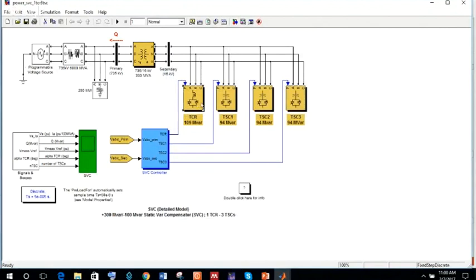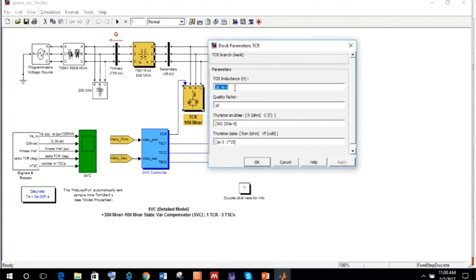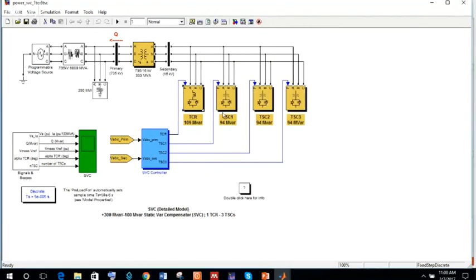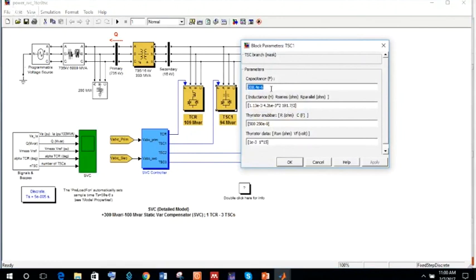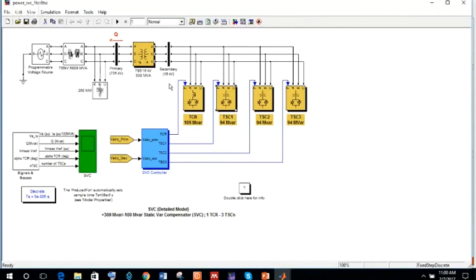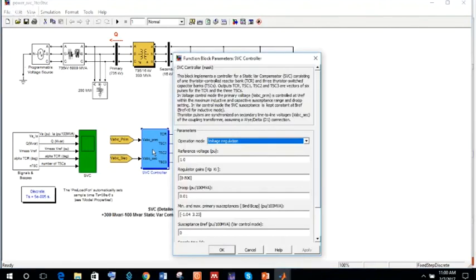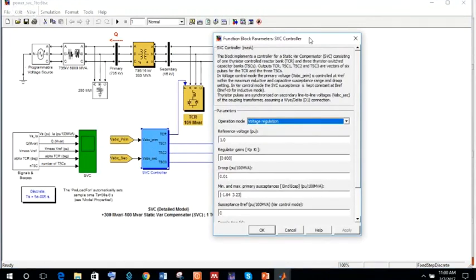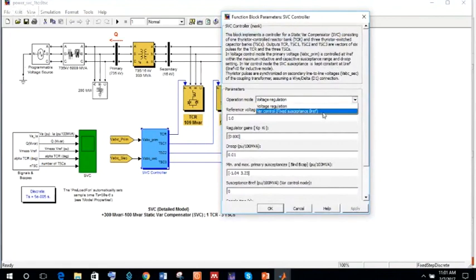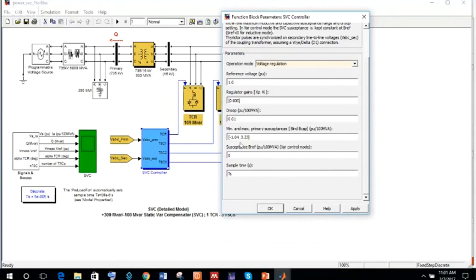Okay. Here this is capacitor value, inductance value. Here it is inductance value because it is TCR, so that you should mention. Here it is capacitor value that you should mention as per the design. This is the controller. In the controller you have two modes. One is voltage regulation, other is VAR control. That is reactive power. This will give constant reactive power, and voltage regulation will provide you constant voltage, whatever reference you have mentioned. Droop characteristics should be mentioned, and here it is the minimum and maximum primary susceptance that can be provided by the SVC that you should mention.